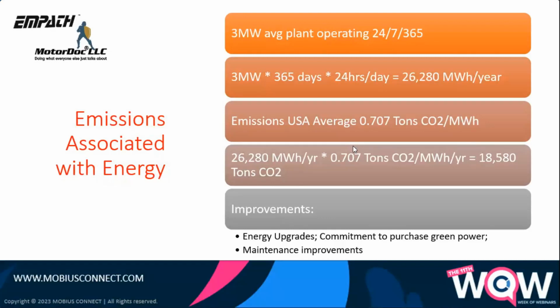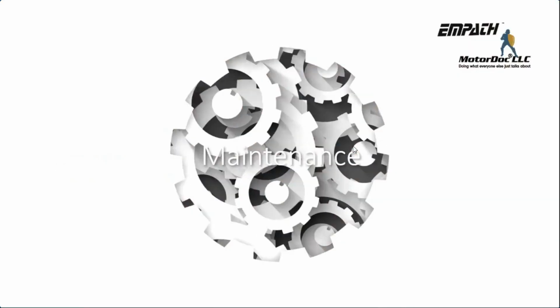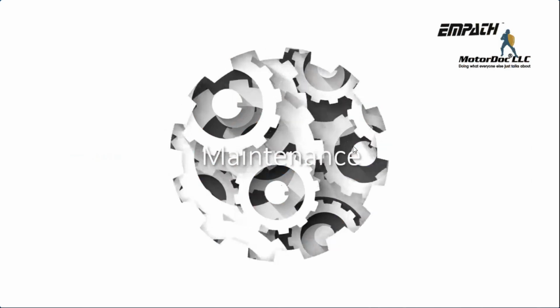So the big one that they had not really paid attention to up to date was maintenance improvements. Now, they made small changes and they got excited when they saw 1 or 2% improvement. We did a study there, so we're going to cover this part, and then we're going to cover power, just taking care of harmonics and things like that. Something that we talk about, but we never do, and it always seems to affect the bearings. And instead of correcting the problem, we put Band-Aids like shaft brushes on the machines. So let's take a look at the maintenance impact.